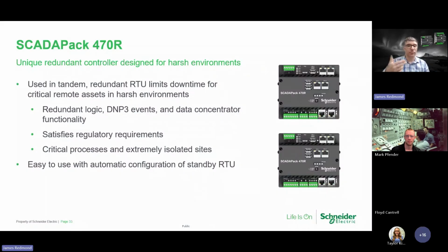The active controller goes down, someone pulls the power, changes the battery, wants to upgrade the firmware or update the application. The standby controller takes over in an almost bumpless way, within a few hundred milliseconds, and your process continues.